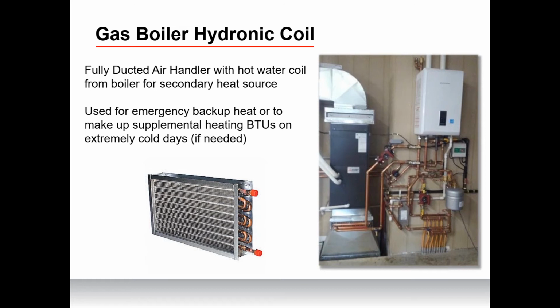So the coil itself would be a third-party source product that you would tie into the boiler system you already have, and then that can tie and be controlled by the air source heat pump. So think of the air source heat pump acting as first stage, and the hot water coil then acting as second stage heat or acting as an emergency backup.